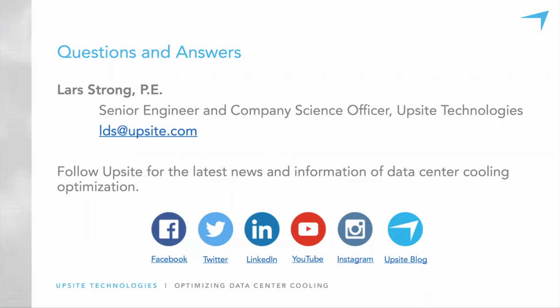Sounds like. Yeah, so it may be a higher percentage than, say, what Sandia Labs was able to create. Maybe it ends up being 90-10, 90% immersion cooled and 10%, or maybe even 95. Those numbers could increase over time as we see both the technology of immersion cooling and the choices for components going into it being designed around that solution, those numbers could go up. But yeah, there will always be a small percentage, or maybe a larger percentage. We'll see how that evolves.